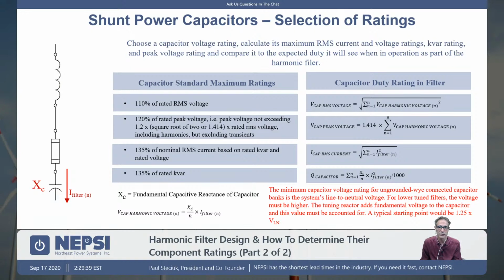So our spreadsheet tool does this. We put in the harmonic current that we expect in the filter, or really the real way of saying it is we put the harmonic filter current ratings in the system. So we're coming up with a harmonic filter current rating. What is the fundamental current rating? What's the 5th? What's the 7th? What's the 11th? What do we want to tell our customers that the harmonic filter is rated for? And those are the values that go into our spreadsheet. Those are the values that are used to choose the actual fundamental voltage rating of this capacitor.